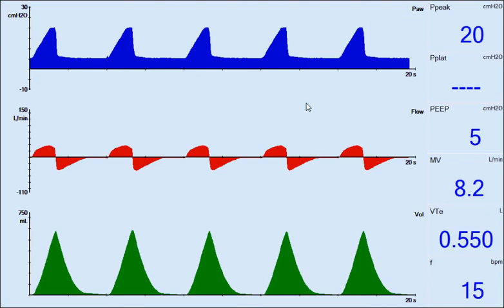A slow rise time may cause increased work of breathing for patients with a high inspiratory drive and decreases mean airway pressure, alveolar fill-in time, and area under the curve which may decrease delivered tidal volume.